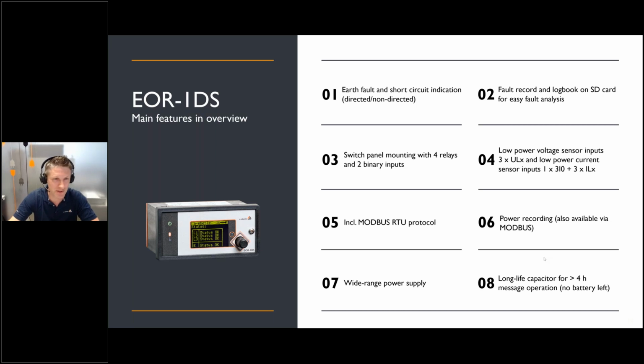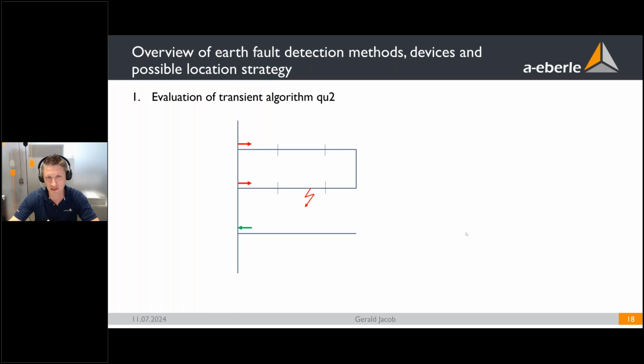Okay, this was just to introduce to you our device EOR1DS for simple secondary substations, which is quite an attractive solution for these stations. To the EOR3DS, we will come in the next chapter. Now I just want to shortly introduce to you the strategy that a lot of DSOs are using together with these earth fault indicators. As an example, here is a bus bar with 3 lines. The first line is just a single feeder, and then the two other feeders are switched in a ring manner, as you can see. And we have an earth fault indicated by this arrow.